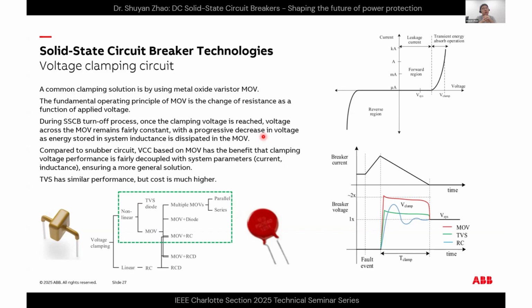For example, if each event has a really huge current, up to a few kiloamps, and it comes with a system inductance up to millihenries, it may fail after only tens of short circuit interruptions. But if we properly design the voltage clamping circuit, for example, paralleling more of those energy absorbing components and making sure the current is evenly distributed in each event, the life will be extended. For example, if each MOV only handles a few hundred amps at a few microhenries of line inductance or impedance, this can work properly for millions of operations, or at least tens of thousands of operations, with no reliability issue. Does that answer the question? Yes, thank you so much.